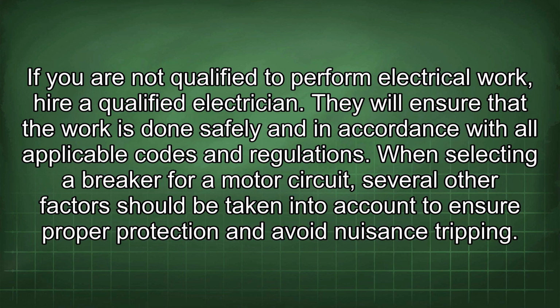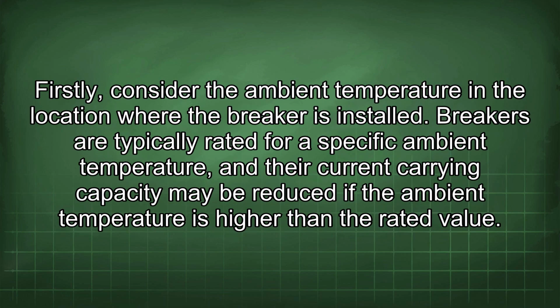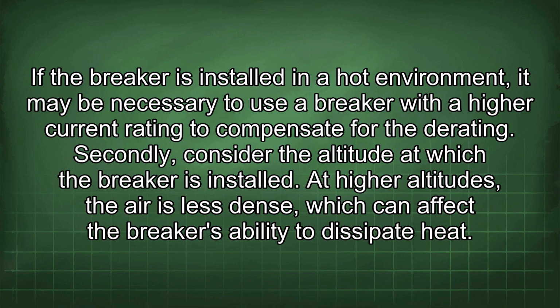When selecting a breaker for a motor circuit, several other factors should be taken into account to ensure proper protection and avoid nuisance tripping. Firstly, consider the ambient temperature in the location where the breaker is installed. Breakers are typically rated for a specific ambient temperature, and their current carrying capacity may be reduced if the ambient temperature is higher than the rated value. If the breaker is installed in a hot environment, it may be necessary to use a breaker with a higher current rating to compensate for the derating.